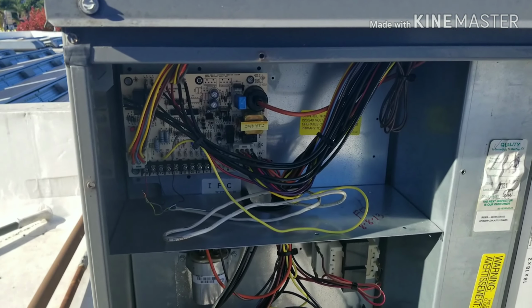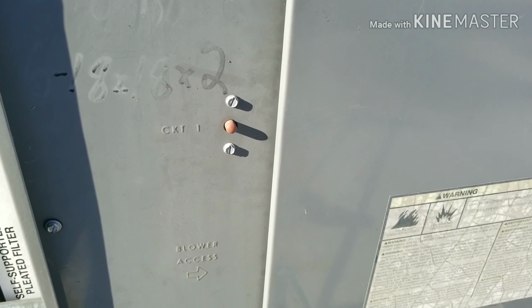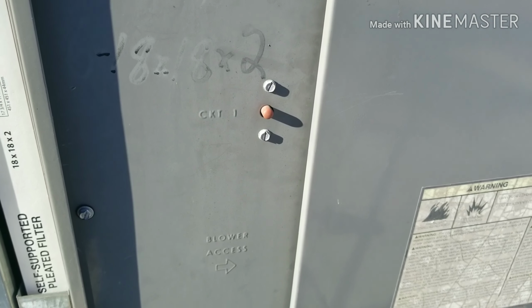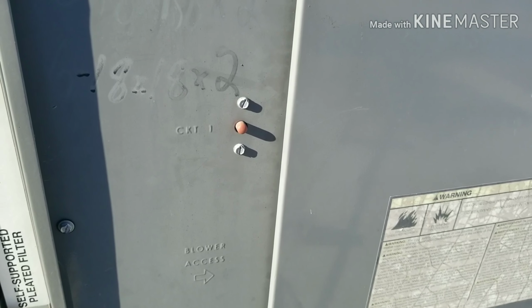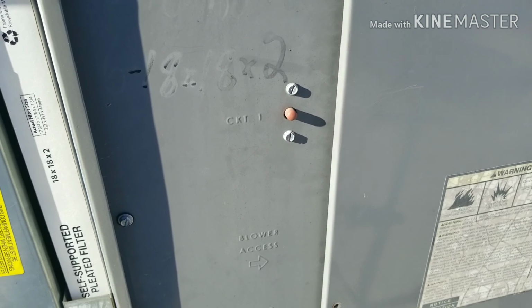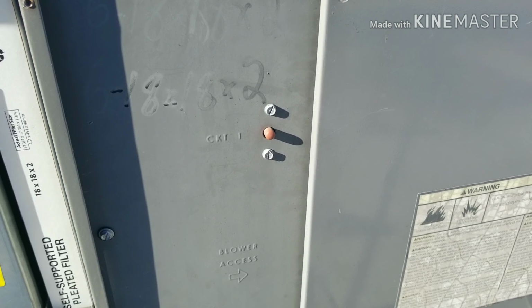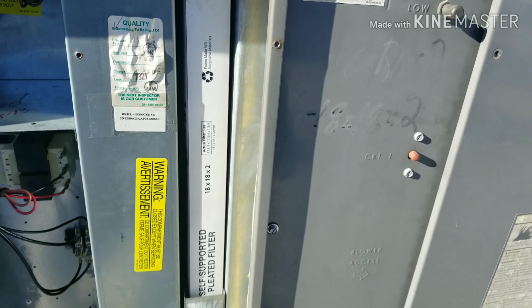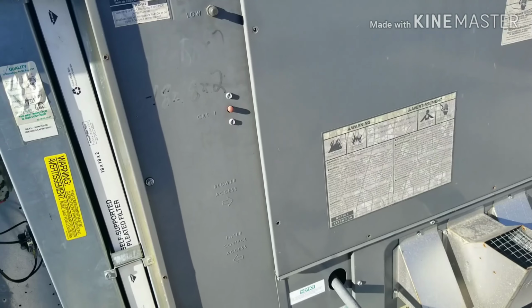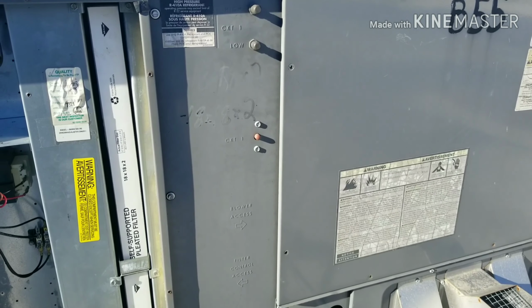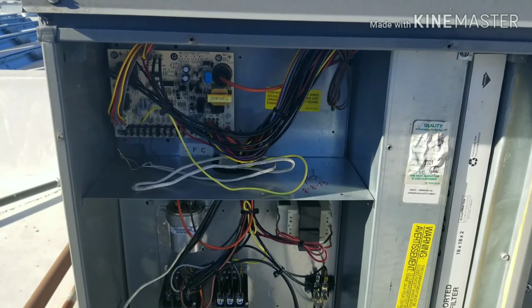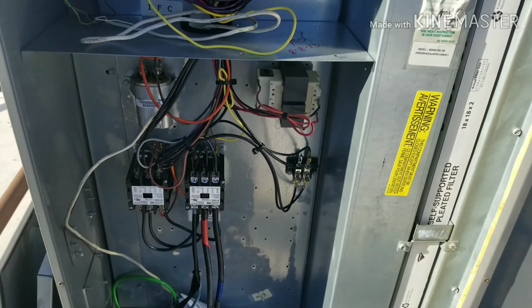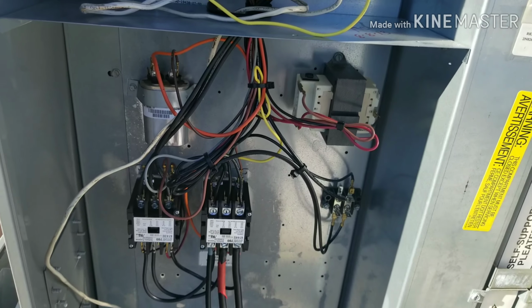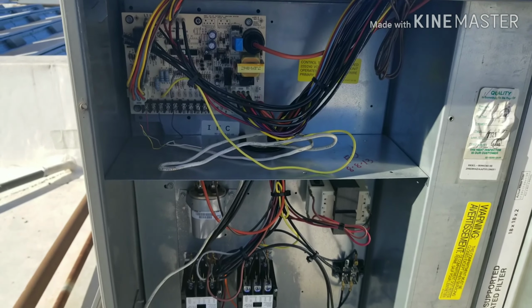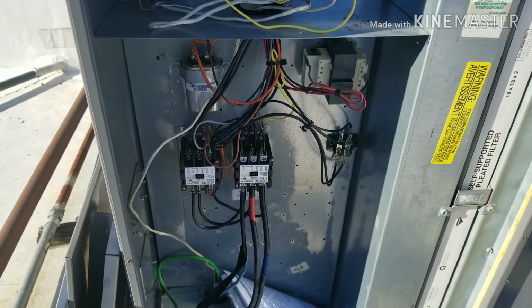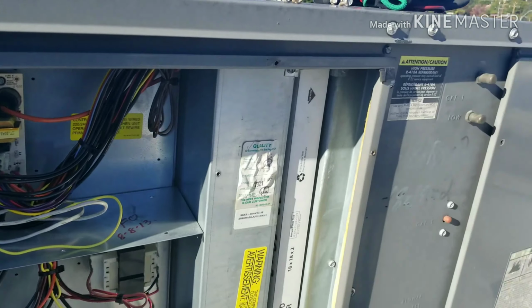So yep, this is a pressure switch, circuit 1. Pretty much if it trips on a low pressure, you can reset it. But before you reset, you kind of want to find out what happened, right? You just don't reset things and walk away and think that that's all you have to do. Again, be careful with high voltage, guys. This is a 208, and see the fan just turned off right now.